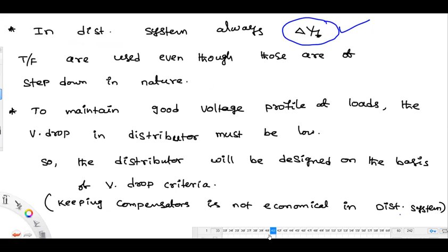Sir, before you said at the distribution level, the primary distribution level of 11 kV will be 3-phase 3-wire. But when we take the receiving substation like 33 kV, 11 kV with delta star ground, it will go for 3-phase 4-wire, no, sir? Yes. Then it should be delta by delta, no, sir? Why delta by delta? Why can't it be delta by star? Already this neutral is grounded, right? Yes, sir. So up to this point, ground is acting as a neutral wire. Means we will run only 3-phase 3-wire with the delta star configuration. From this also you get 3 wires only. Ground is going to act as a neutral wire. Okay, sir. Thanks.